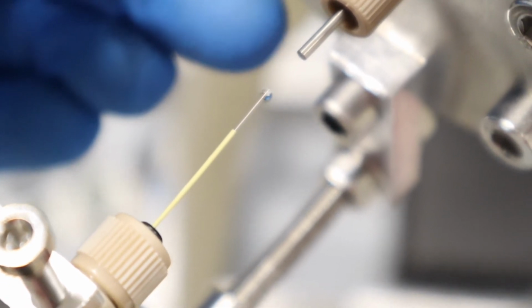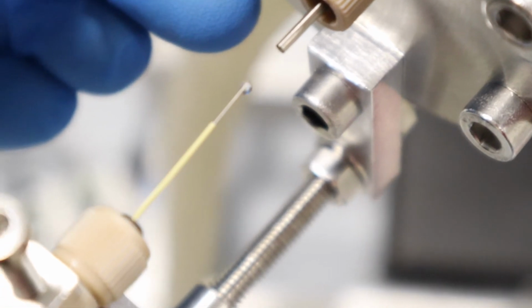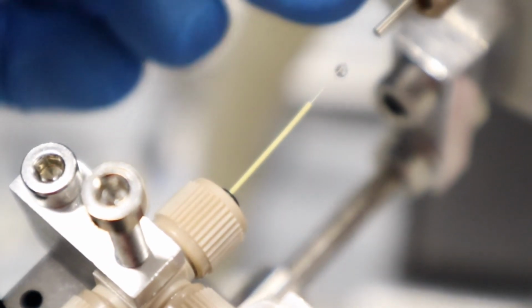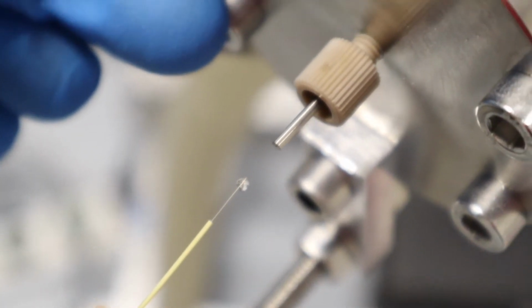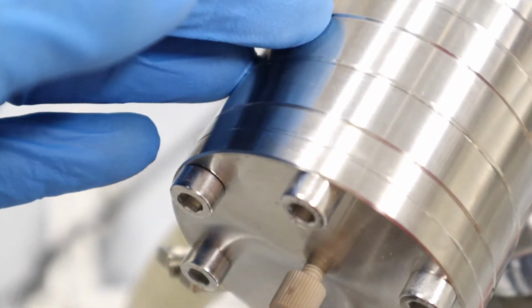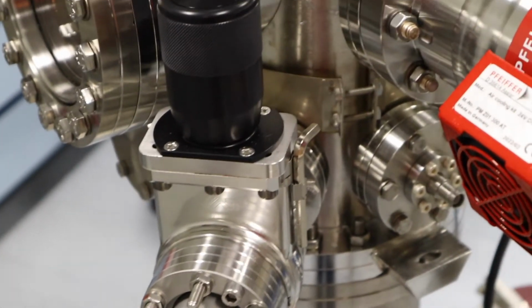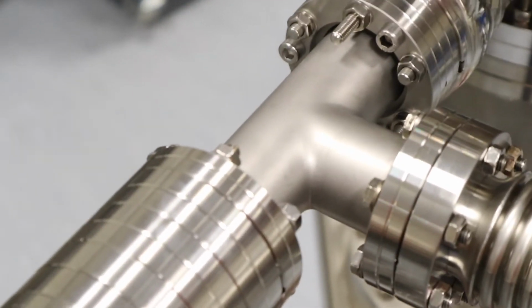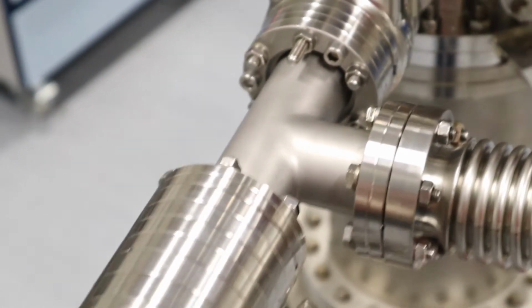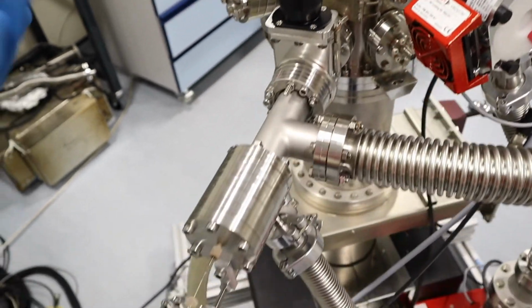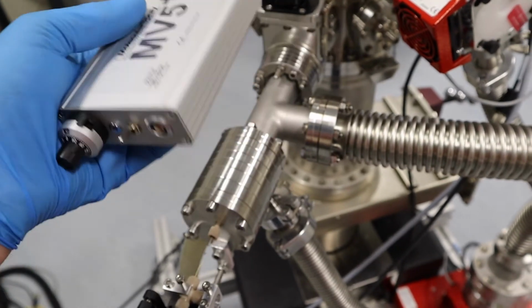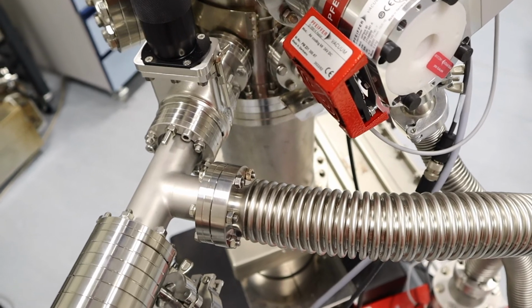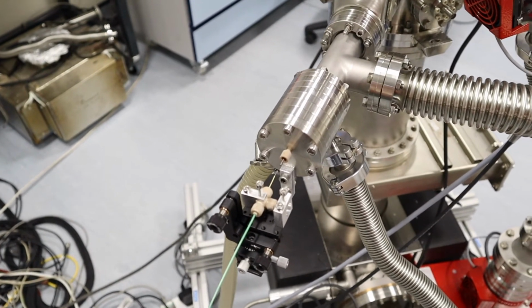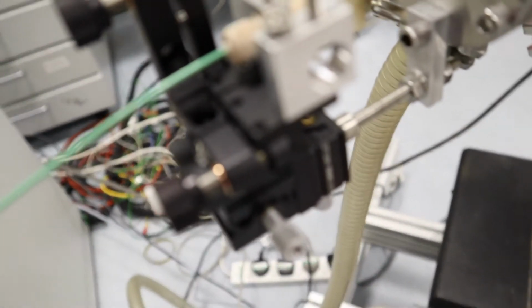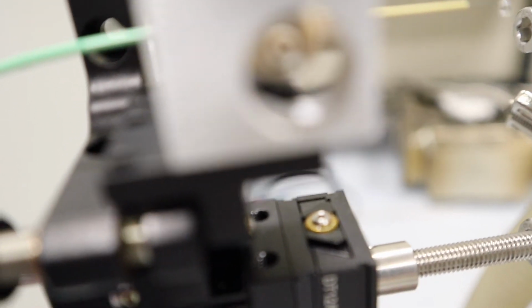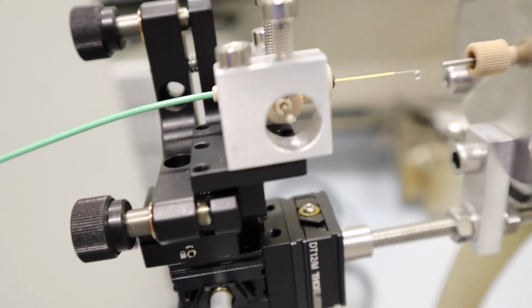Okay, so now we have liquid flow, and now we need to apply the high voltage to that with respect to this entrance capillary. Now the entrance capillary is grounded to the chamber, and the chamber is grounded to the main system, and the main system is grounded to the same ground as the power supply that we're going to use to apply the high voltage, which is this one, and so that shares the same ground through its DC low voltage power supply that powers it. So that attaches to that central pin. This is, you can just see in there, and held in place with this screw.